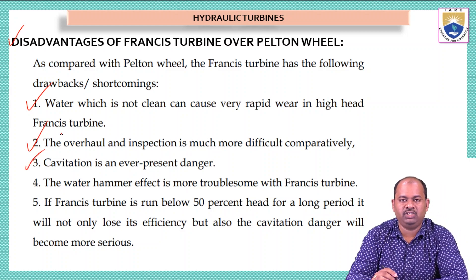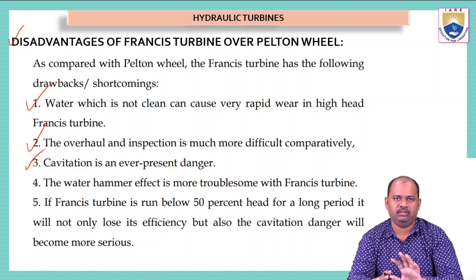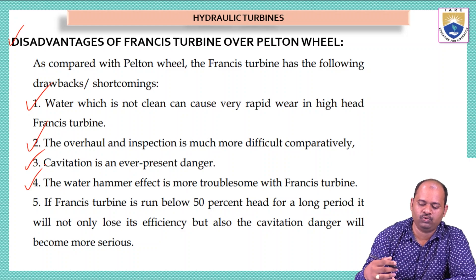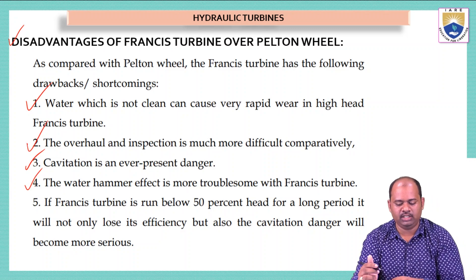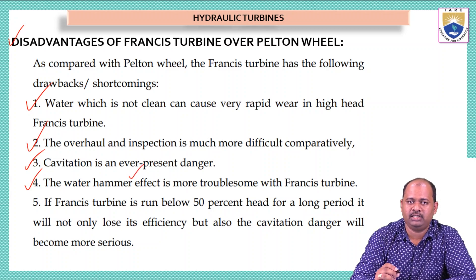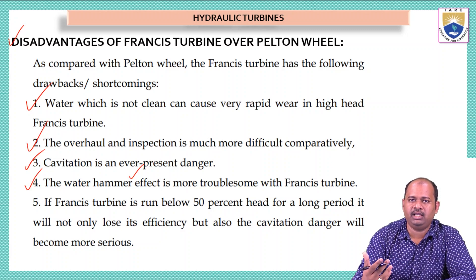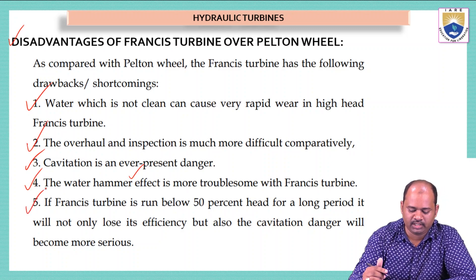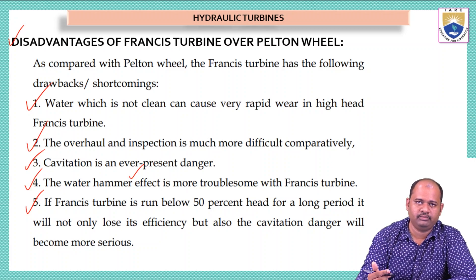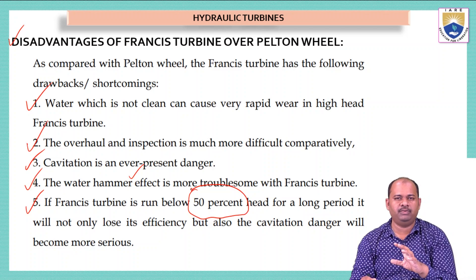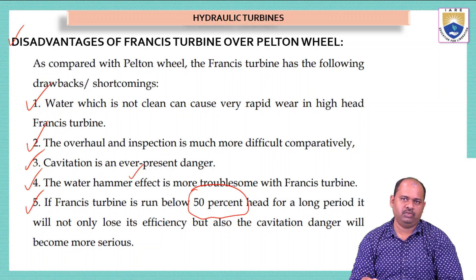Third disadvantage is cavitation, which is an ever-present danger in the Francis turbine — we will study this in coming lectures. Fourth, the water hammer effect is also a danger that can cause the Francis turbine to malfunction or damage mechanical parts and must be controlled. Fifth, if the Francis turbine runs below 50% of the operating head for a longer period, it will not only lose efficiency but the cavitation danger also becomes more serious, and the turbine may need to be replaced.